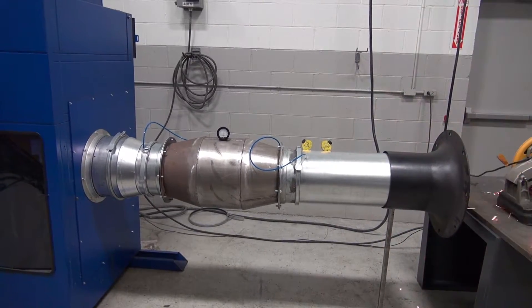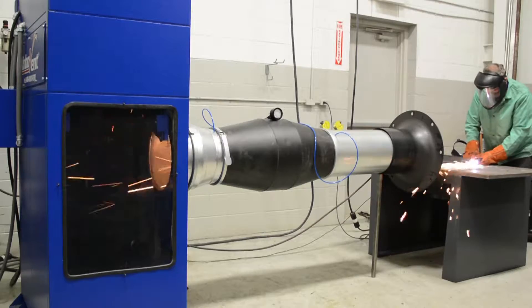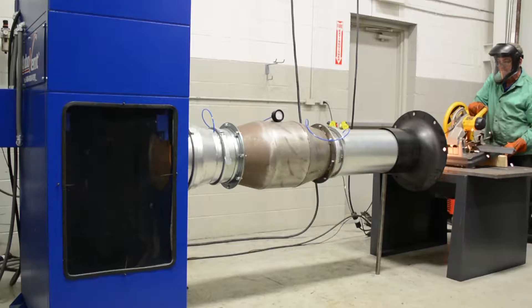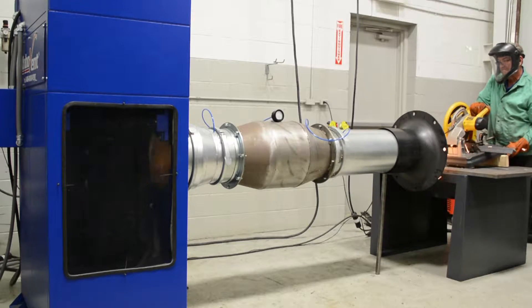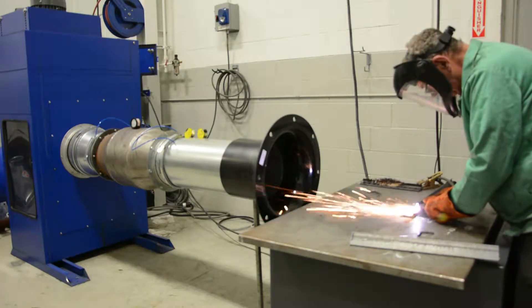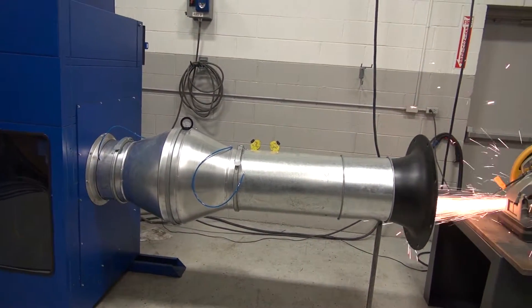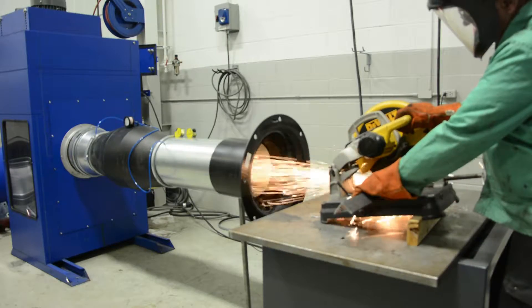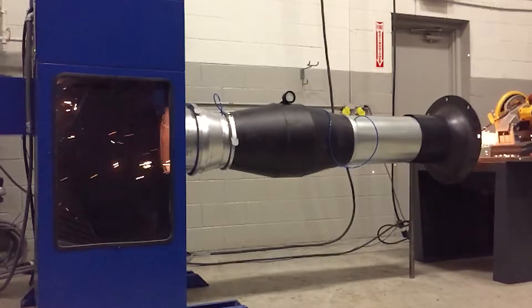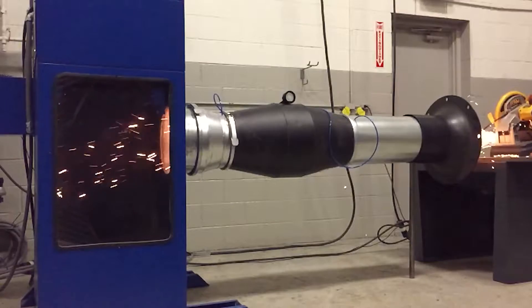Over the years, engineers have designed many different spark arrestor systems, some more effective than others, but all have had drawbacks. Some require regular cleaning, driving up maintenance costs. Others create high restriction to air flow, ramping up energy costs and also shortening the filter life of the collection system. Worse yet, many do not kill the sparks effectively, heightening the risk of a collector fire.